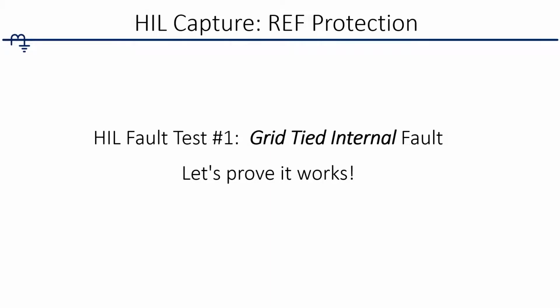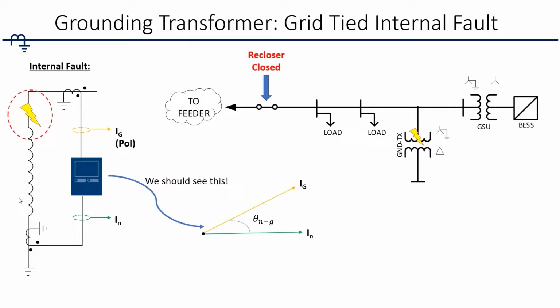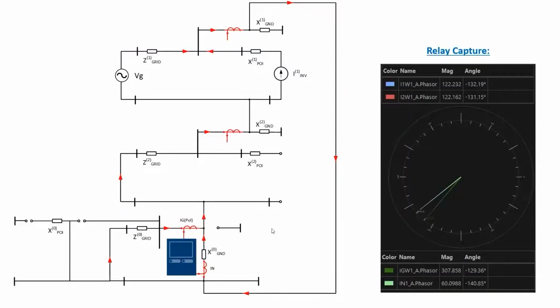So let's prove this thing actually works. Me in particular, I like actually seeing it when we do the simulation, which is pretty cool. So here's a HIL test we did with Typhoon, and we ran an internal fault test. We placed a fault near the top of the winding, right at the very tip, just inside the CT. It wasn't deep inside the winding or anything like that. And like we said earlier, you would expect to see this angle be fairly narrow. During this simulation, the recloser was closed, so the point of interconnect was tied back to the utility, so it's grid connected at this time. So this is kind of what we expect to see, a pretty narrow angle here.